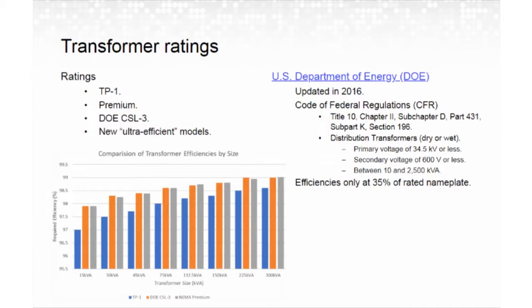In 2002, NEMA issued a standard for transformer energy efficiency in reaction to the U.S. Department of Energy guidelines. This resulted in the TP1 classification that has been widely used since. In 2016, another update changed the required energy efficiencies for several transformer classifications, including TP1, CSL-3, and NEMA Premium. The graphic shows required energy efficiencies for the three classifications at several kVA ratings.